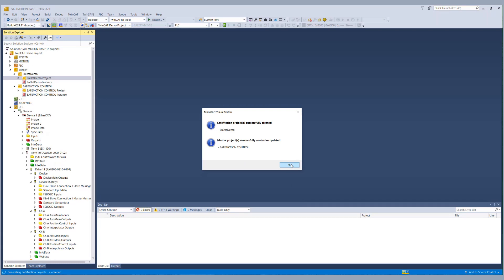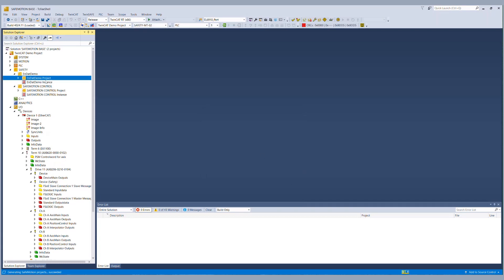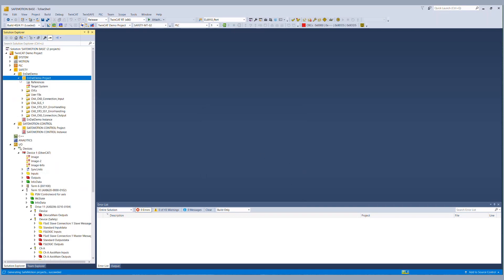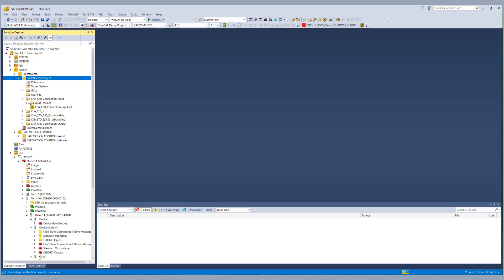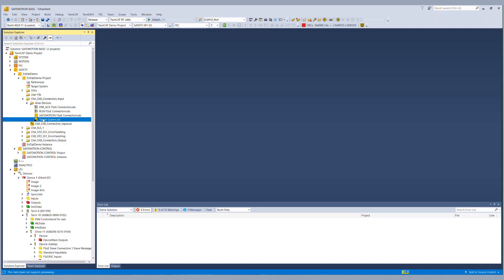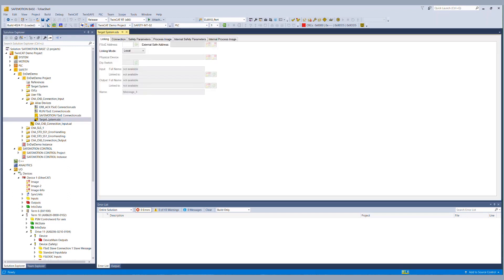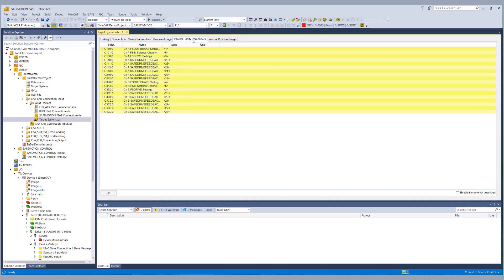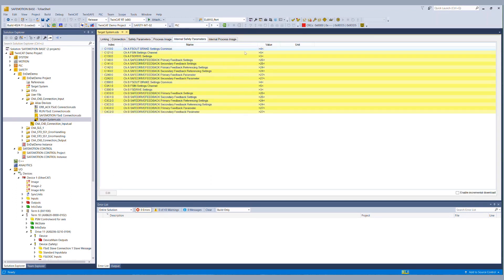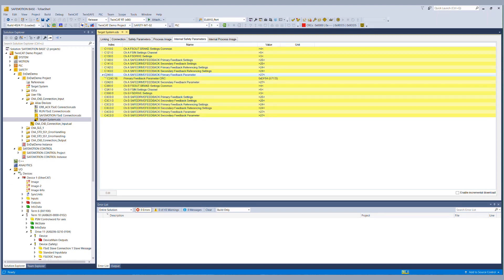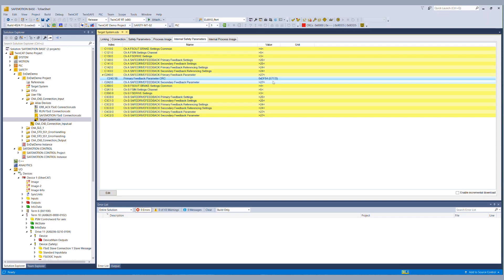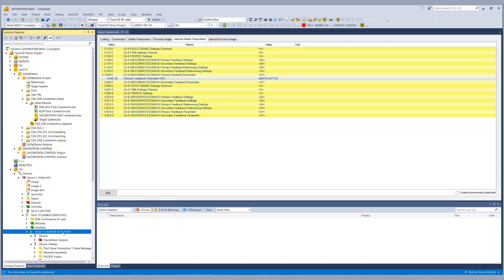The safety project we now have is an AX8000 safety project which is configured for OCT safety multi turn for channel A. So if we go to the target system and to the internal safety parameters we go to the object C2A0 where we see the primary feedback parameters and within that object we have the primary feedback parameter of the CRC but of course that CRC is calculated for OCT safety so in order to convert it to an encoder safety project with EnDat 2.2 we have to get the EnDat 2.2 CRC.